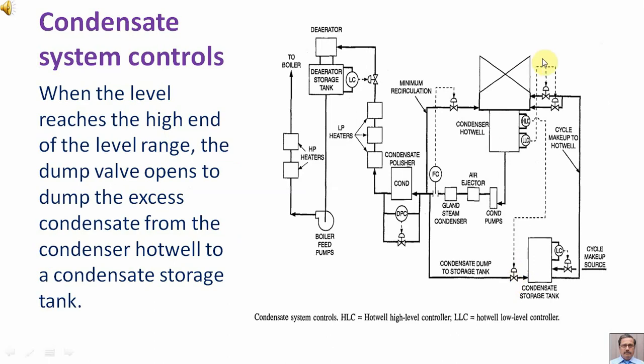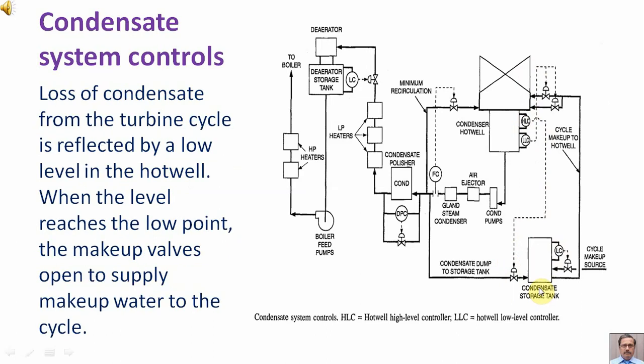The hot well level can be controlled within a safe range by modulating make-up and dump control valves. When the level reaches the high end of the level range, the dump valve opens to dump the excess condensate from the condenser hot well to a condensate storage tank. Loss of condensate from the turbine cycle is reflected by a low level in the hot well. When the level reaches the low point, the make-up valves open to supply make-up water to the cycle.